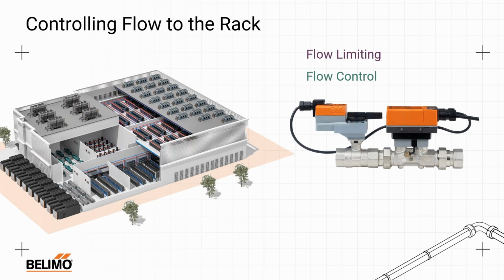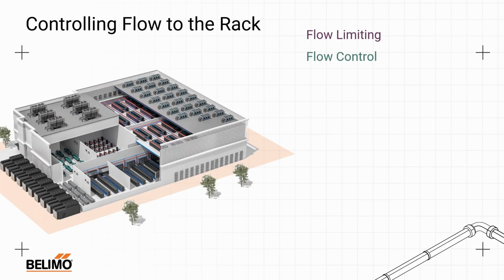So the EPIV from Belimo allows us to read real-time flow data. So not only can you tell it I want 10 gallons a minute going to your rack, you can verify that you're getting it. And it's also a reprogrammable device, so you can tell it, hey, we no longer want to do 10 gallons a minute. Maybe we can do 13 or 14 gallons a minute based on the new servers that we put in, or the new technology that's in place, or just the fact that next year NVIDIA is going to come out with some new animal that we don't know what that is yet, and that would probably have more heat density than we have today. So we went from flow limiting to flow control. That gives us this extra versatility. And then we're going to talk about differential pressure control.